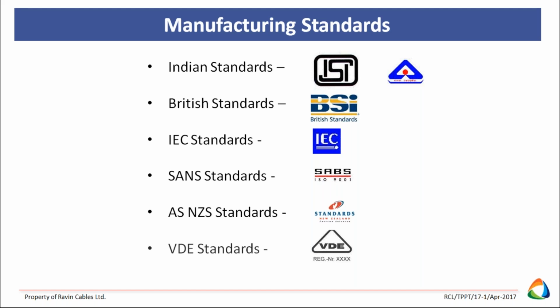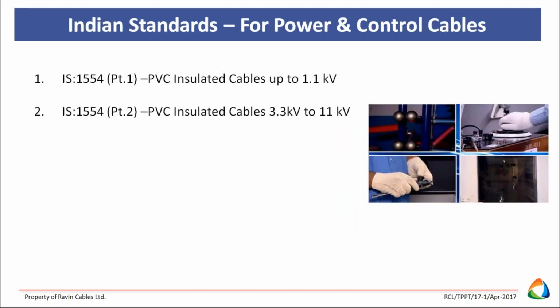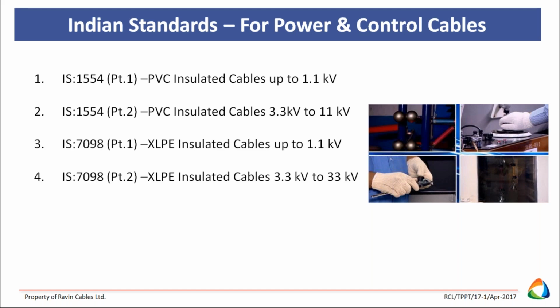However, these standards are available for various products, including cables. Since we are in India, we maintain the Indian standards. IS 1554 Part 1, Part 2 for PVC insulated cables, IS 7098 Part 1, Part 2 for XLPE insulated cables, but the voltage grade is different, 1.1 kV, 33 kV. Here, what is the basic difference? Conductor material remains the same, aluminum or copper. But in the insulation part, if it is PVC, then it is a PVC insulated cable. If it is rubber, then a rubber insulated cable. Suppose it is XLPE, then it is an XLPE insulated cable. The rest of the parts are the same. Conductor same, difference only in the insulation part, PVC or XLPE.